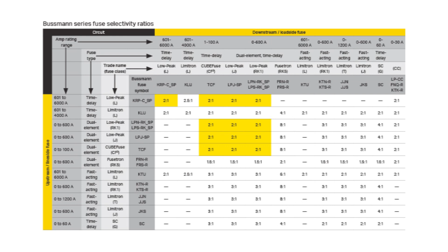The National Electrical Code requires selective coordination for critical loads on specific systems, including elevator circuits, campus-style fire pumps, emergency systems, legally required standby systems, and critical operations power systems. The NEC defines selective coordination as restricting the outage to only the circuit affected for the full range of available overcurrents and for the full range of opening times associated with those overcurrents. The fault current must be known and considered in the analysis for selective coordination.